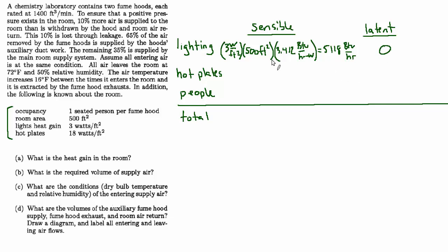And then we have the hot plates, which I was prepared to assume was completely sensible load. But I cheated and looked at the answer solution, and they're allocating two-thirds of the load to sensible and one-third to latent. I guess the assumption is that the application of a chemistry lab would be using hot plates to boil some water or do something that produces latent load in the room. So I'm going to go with their assumption.